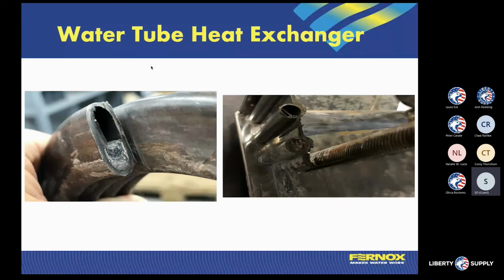So the inside of that heat exchanger, this is what that would look like. So you have the buildup. So the bottom side of that heat exchanger on the picture on the left, we're looking at the buildup. So that burner has to now fight through all of that sediment and all of that buildup. So at that point, it's exposing the metal to extreme temperatures that it's not designed or meant to be around.